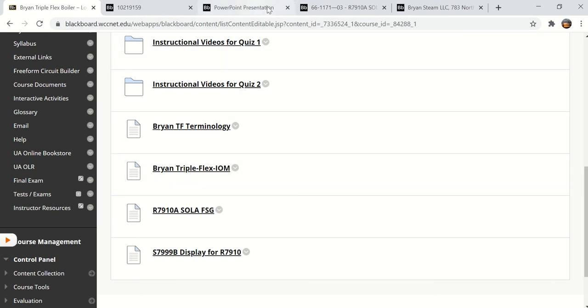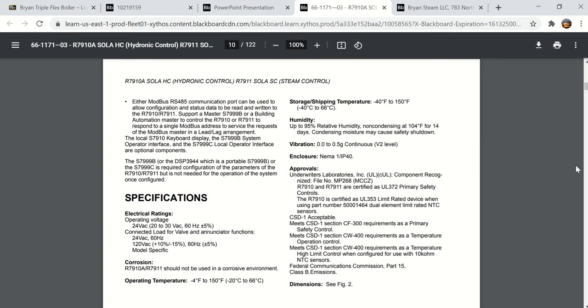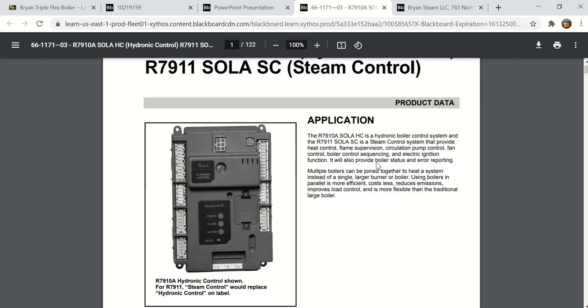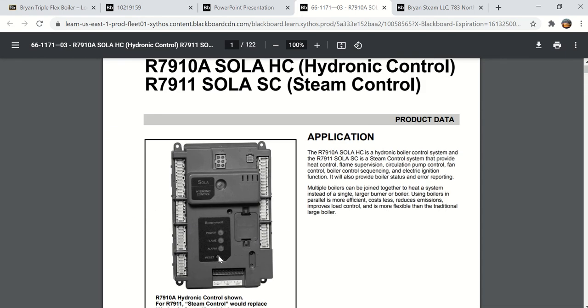So let's go over a few things here. I wanted to go over some of the particulars about the Honeywell SOLA controller. I mentioned a reset button. That is actually right here on the front of it. It has indicator lights for power is on, flame is on, and if it goes into alarm, which means it needs to be reset. When you looked at all the wiring that came in here on the right or the left-hand side, most of that was 120 volt. Most everything on this side is either low voltage or 24 volts or sensor inputs.